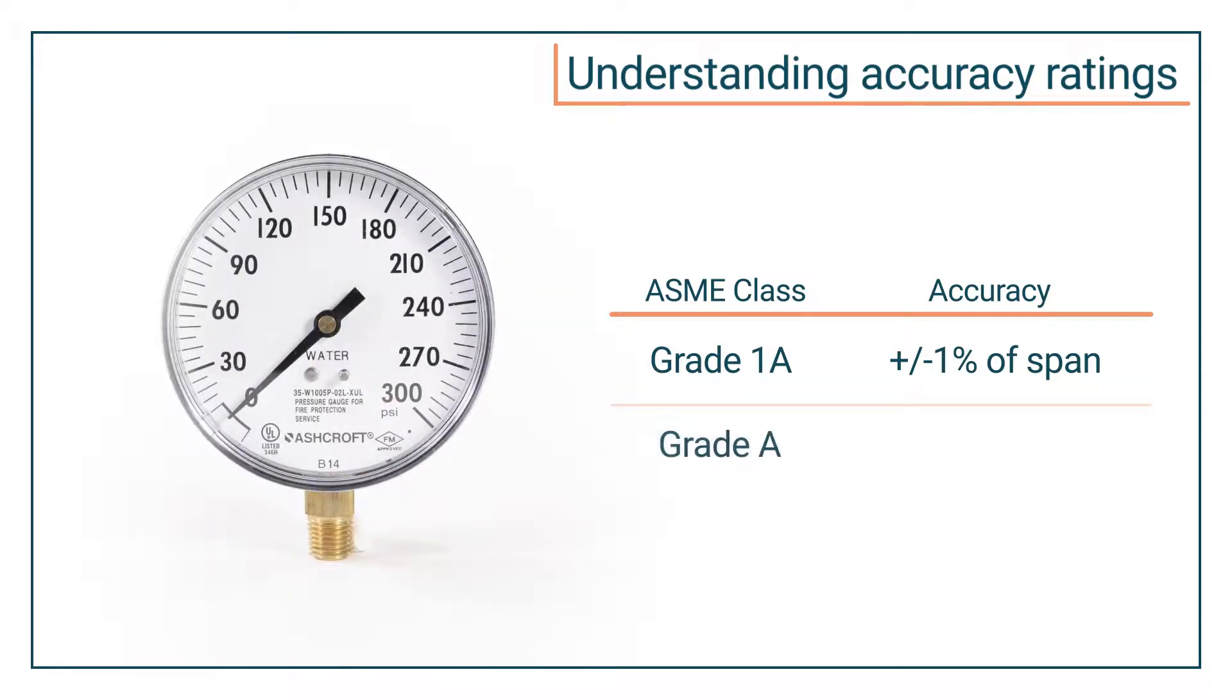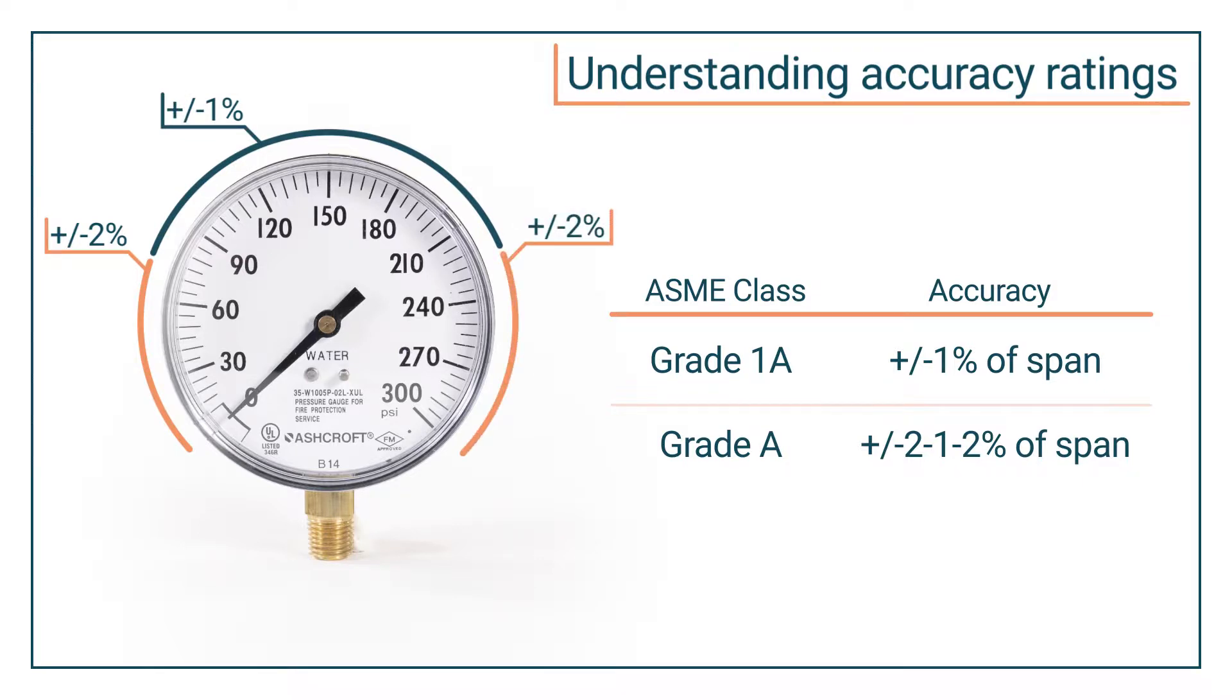Varying range gauges use a series of three numbers, like plus or minus 2, 1, and 2%. This means the first quarter of the range will have an accuracy of plus or minus 2%. The middle half will improve to be plus or minus 1%, and the last quarter range will have an accuracy of plus or minus 2%. You can see how the ASME class relates to the accuracy of the gauge.